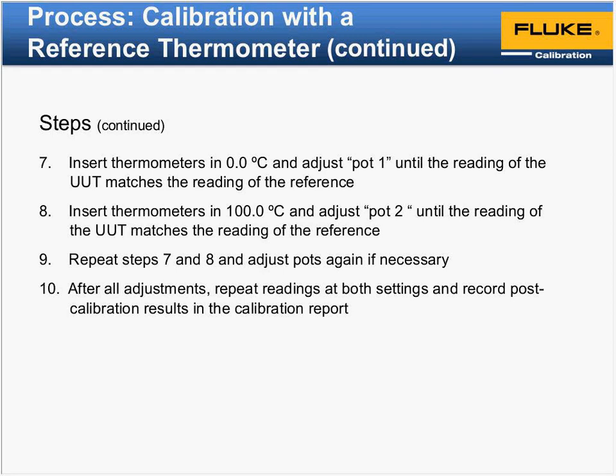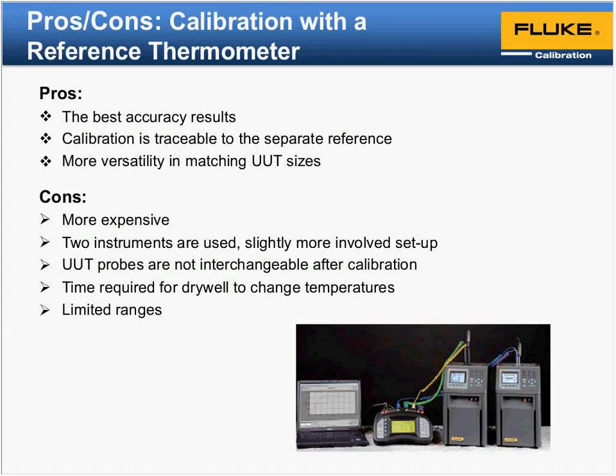If you need more range, the next jump you can make, and you're going to lose some accuracy versus the thermistor over that range, is to gain temperature range. Next kind of move that you can go is RTD, and again, there are various level classes, all the way up to a very specific coefficient. There's also Callendar-Van Dusen values to interpret the probe's resistance to temperature. Again, then moving on from there, for more range and more accuracy, you move to what they call an SPRT, or standard platinum resistance thermometer, which is a different way they build the sensor, typically what they call strain-free. So again, accuracy, but working with that level there are some additional pieces regarding a water cell to plot your drift and different things.